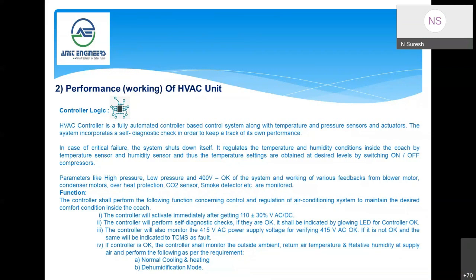The controller shall monitor the outside ambient temperature, return air temperature, relative humidity. So whatever the temperatures it is programmed, the desired temperatures, if that is having a difference, then accordingly the system will function. Suppose when the system is on, and the ambient temperature and the inside temperature is less than 17 degree, obviously it will go for heating mode. So this master will say what mode system has to work based on the parameters, temperature, pressure.